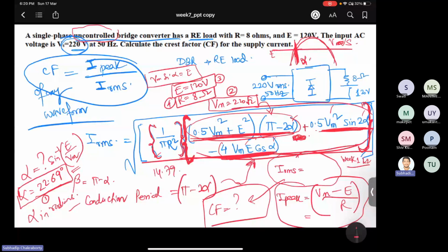And this inside, if you calculate total value, it will come out as 44219. This total second bracket, whatever is in the second bracket, is 44219. And when you divide it with pi into r square, 44219 divided by pi into 8 into 8, it will come as 219. So square root of 219 is the answer. Just check where you did wrong. You will get around 14.8 amps as the RMS.